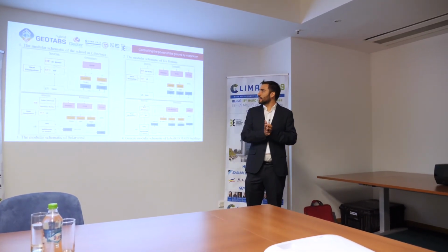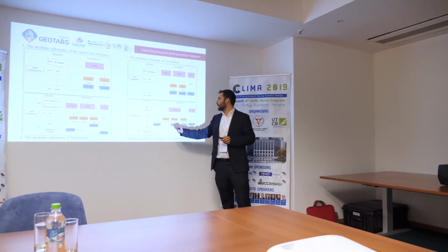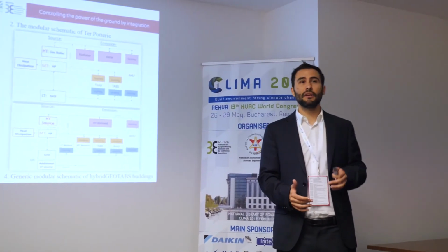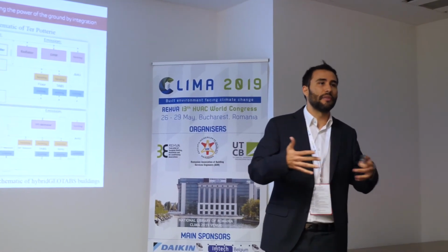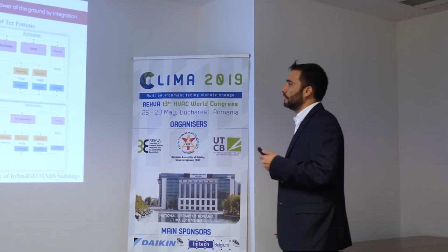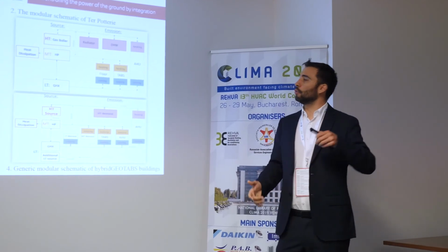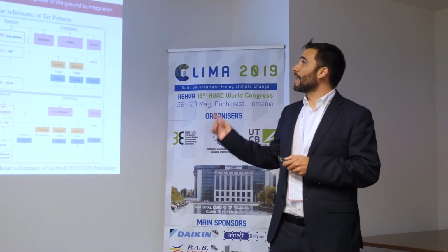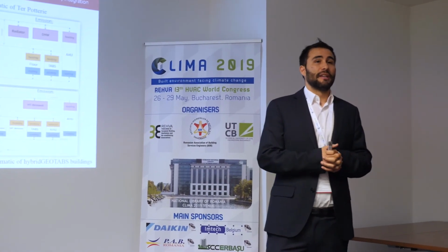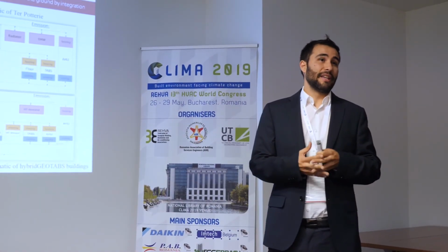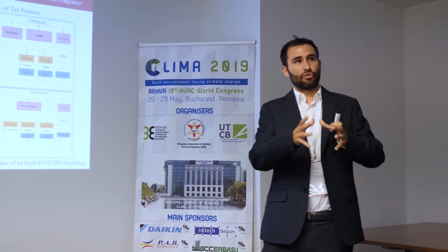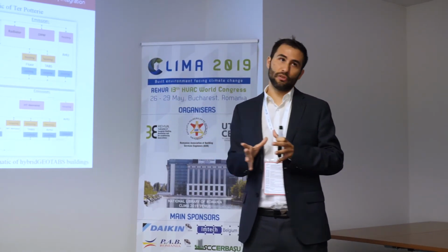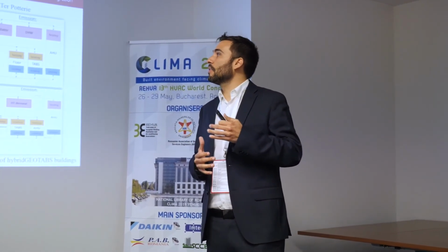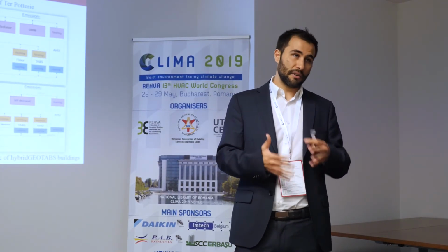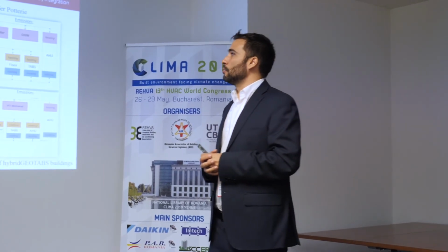For the emission side, the same. Normally, we cover low temperature demand and medium temperature demand with TABS, air handling units, or underfloor heating and cooling, and we cover high temperature demand for domestic hot water or radiators. The objective in the GEOTABS project, searching for the major efficiency of the buildings, is to use geothermal as the energy source and TABS as the emission source, searching for the major efficiency, reducing the consumption of energy, reducing cost, reducing maintenance and improving the control of the whole system.